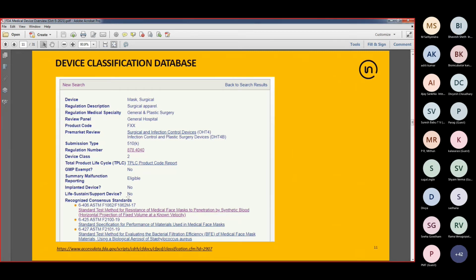And then another important piece of information is submission type. So how do you know what kind of submission you need to make? Actually, before that, you can check the device class. As it appears here, this product is a class 2 device. Now, knowing that the product is class 2 is fine, but how do you know what kind of submission you need to make or you don't need to make to the FDA? For that, you check the submission type. And it says here 510K, so it means you need to submit a 510K submission to FDA before placing this type of product in the US market. Basically, gain FDA's clearance to commercialize this type of product in the US.